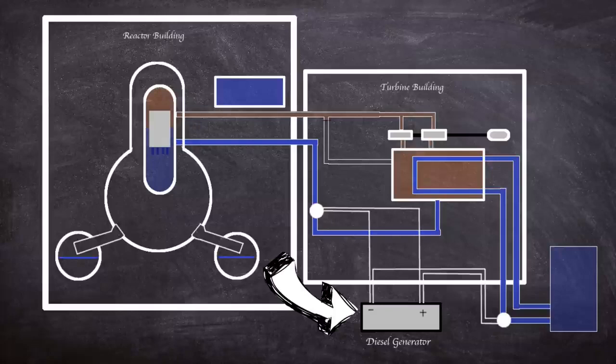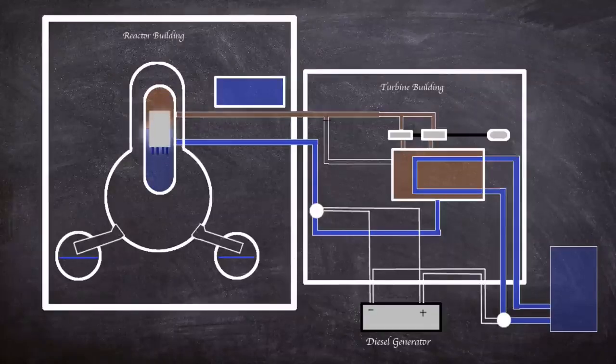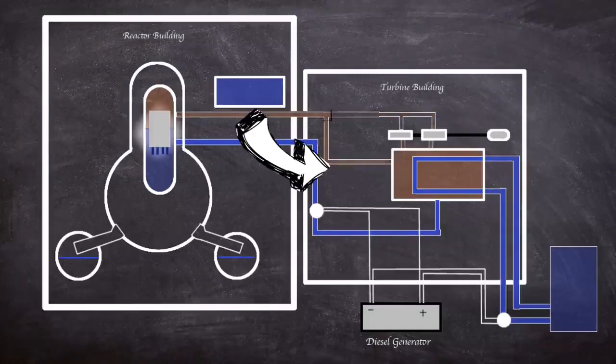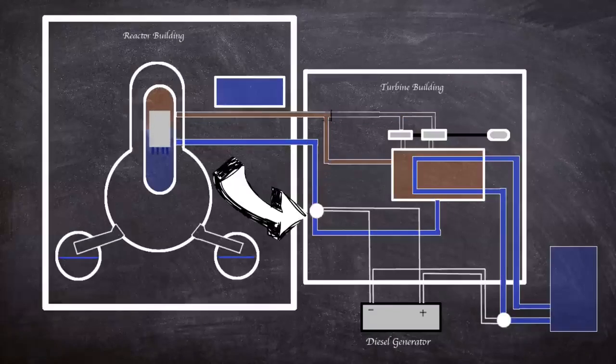Even after shutdown, the reactors needed power to monitor and pump coolant through the cores, as after fission the fuel elements still provide decay heat strong enough to cause fuel element melting. To help with the cooling, in normal shutdown the turbines are bypassed and the coolant in steam form goes straight to the condensers, after which it is pumped back to the core completing the cycle.